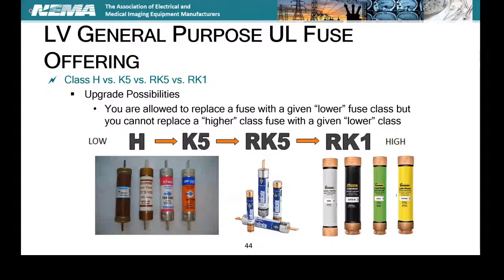But again, you really can look at the installation. If you see that gray fuse, you see something that doesn't have a rejection feature on it, you know you can get more current limiting. And what that means is lower incident energy, lower damage to the equipment that you're supplying power to, which is really, if I can limit the damage, I limit downtime, I limit the cost to repair, I limit the time to repair, the whole bit. So the faster acting just does a lot of great things all the way around.